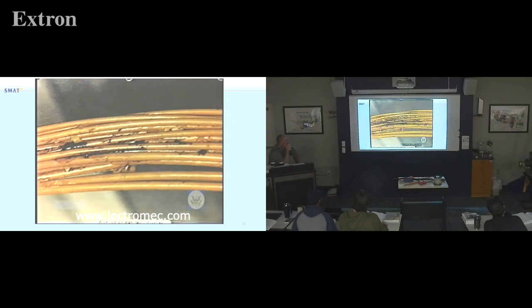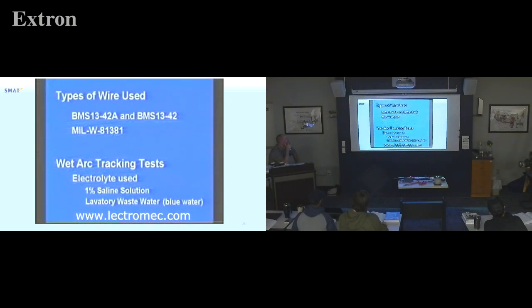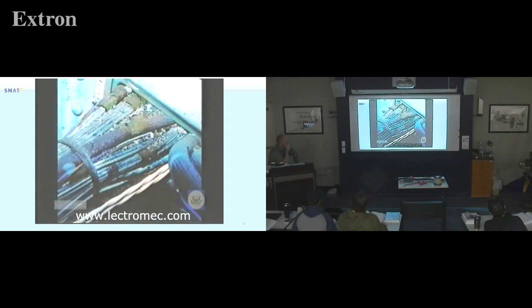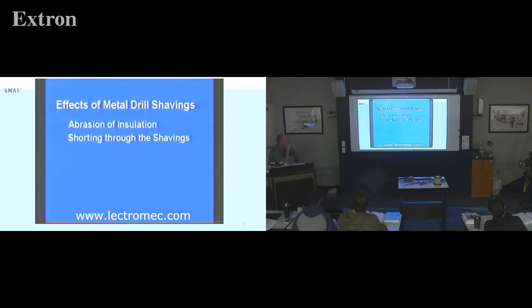This photo shows an example of carbon buildup on 81381 type wire. The electrolyte used for these tests was a 1% saline water solution. Wet arc track tests were repeated with lavatory waste known as blue water. The Safety Board investigation documented numerous cases of metal shavings on wire bundles and between strands, and was interested in examining the effects of metal drill shavings on the wire insulation in abrasion tests. One test measured the damage caused to the insulation by the metal shavings during abrasion of the insulation. A second test recorded the properties of short circuits between wires that the shavings created.